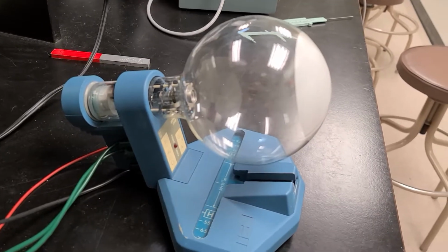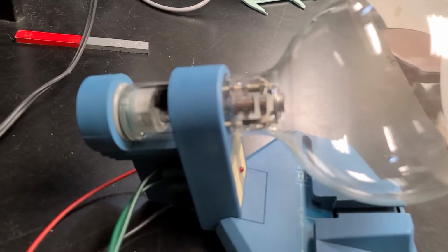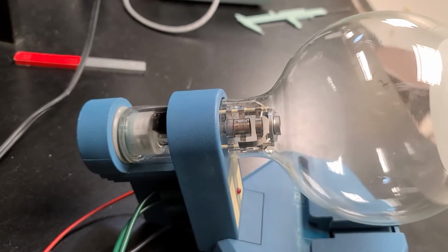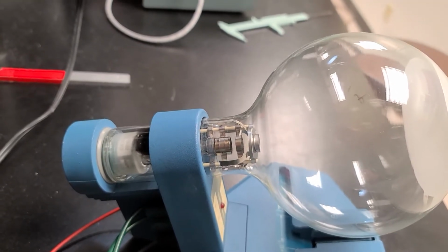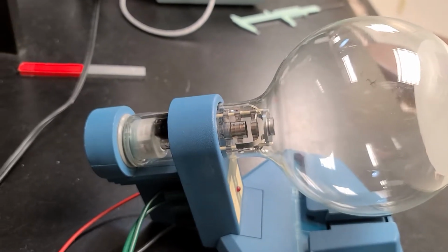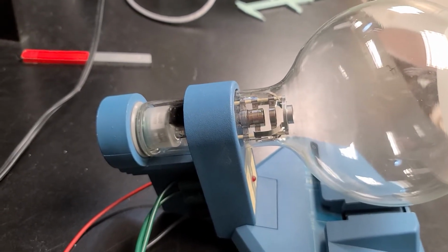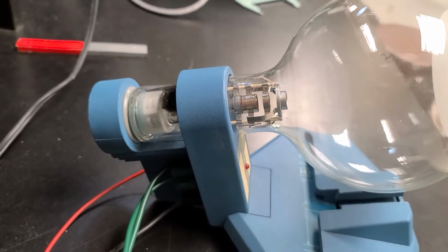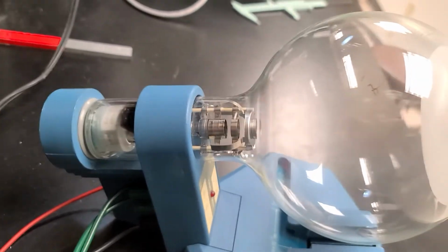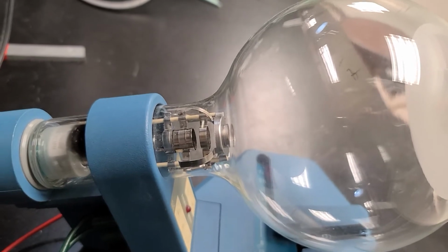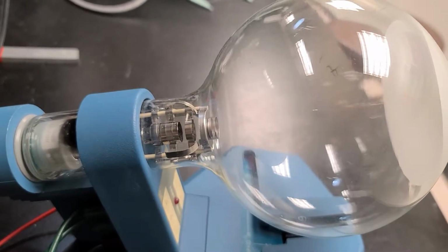So this is a vacuum tube where basically we have some tungsten filament somewhere inside. And the tungsten filament generates electrons through thermionic emission, right, Doug? Yes, sir. It's called thermionic emission or thermal excitation of electrons through some tungsten. And these electrons are accelerated through some acceleration plates between the cathode and the anode, and then they gain the accelerating voltage which is generated by this high voltage power supply.